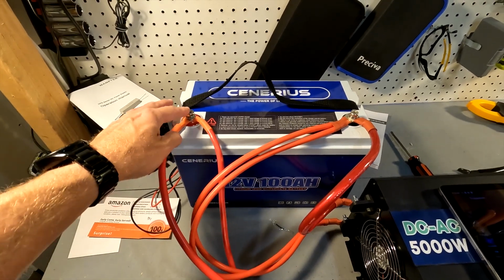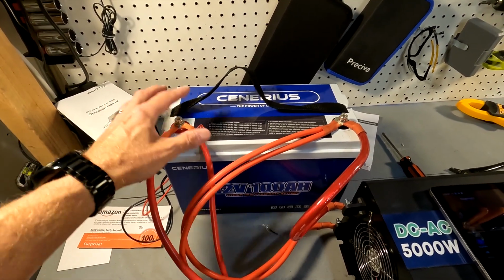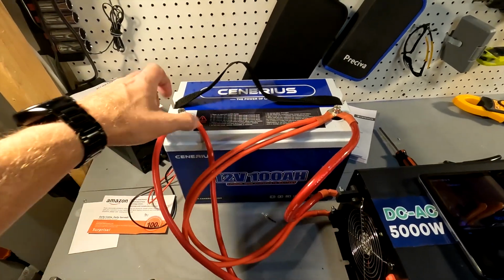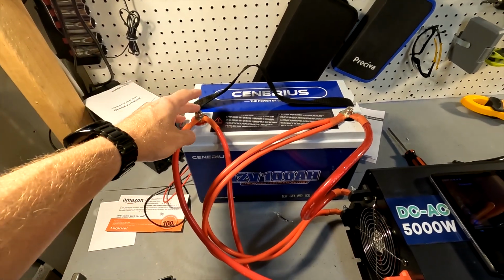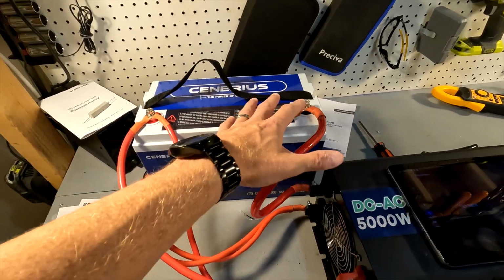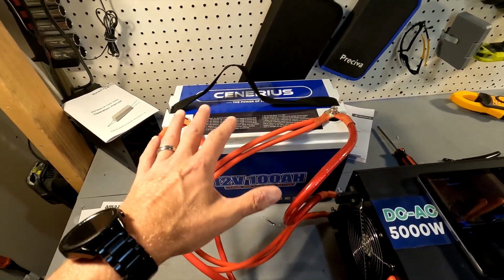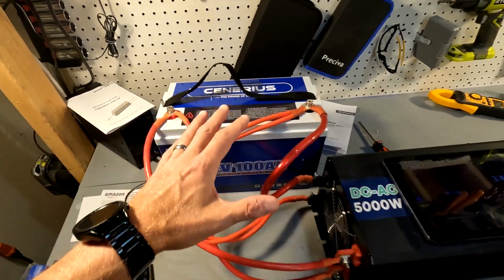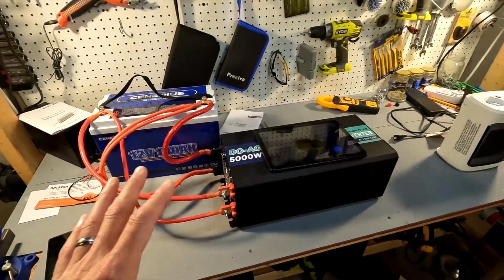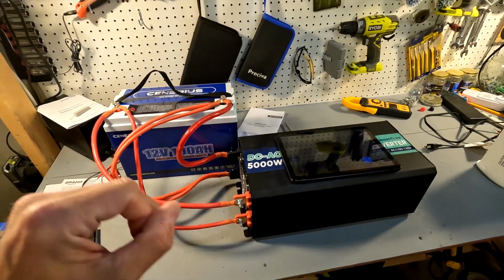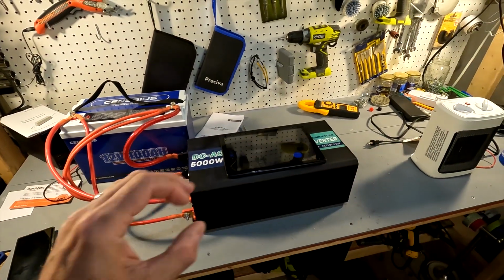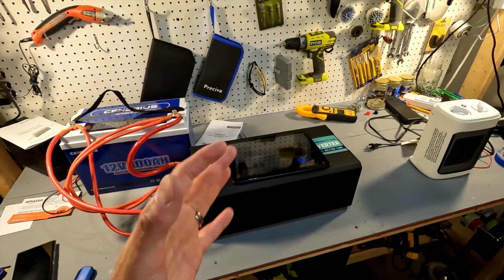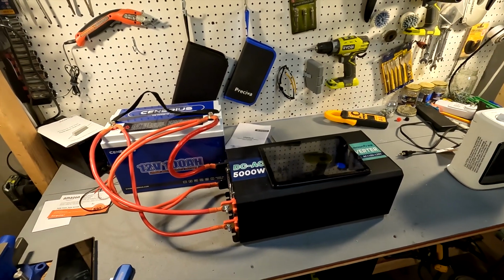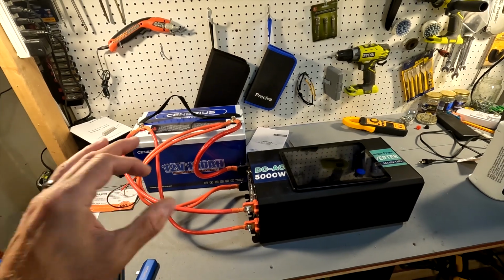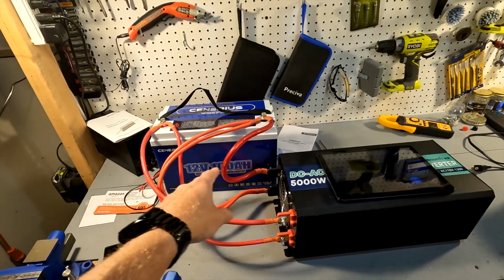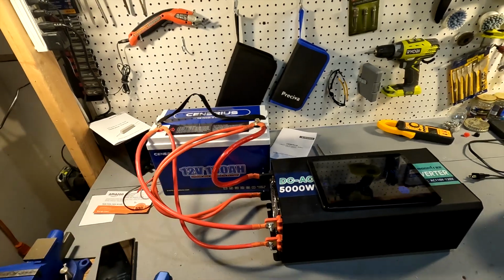I'm thinking, I wonder if these are still going to get really hot now that we have all the proper cabling, because those battery clamps were just clamped on, not a very good connection. Nothing was tightened. So I'll be interested to see if these still get well over 300 degrees after a few minutes of running this heater, or if everything's going to stay cool. We're going to go ahead and just run this again and make sure we can run the 5 minutes, using a thermal camera on everything to make sure it's staying cool, and not seeing hot spots on the front or top of the battery.